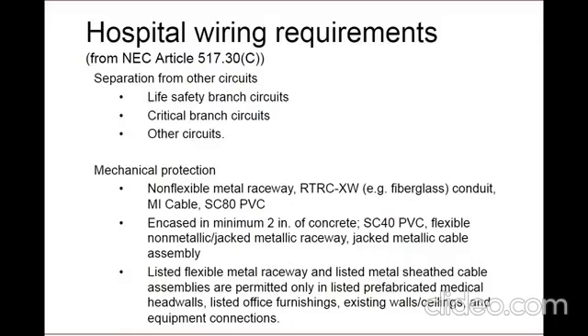Notwithstanding that, there are 5 wiring methods permitted. The first is non-flexible raceways, type MI cable, type RTRC-XW, or Schedule 80 PVC conduit. For those that may not know, RTRC-XW is fiberglass conduit. It's expensive. The second is where encased in at least 2 inches of concrete, Schedule 40 PVC, flexible non-metallic or jacketed metallic raceways, or jacketed metallic cable assemblies listed for installation in concrete.